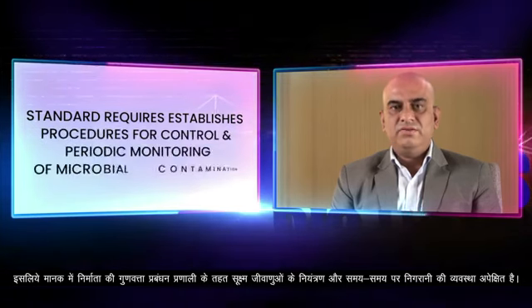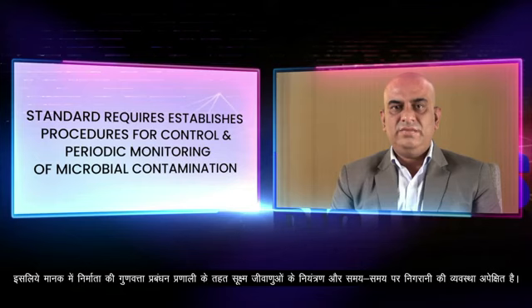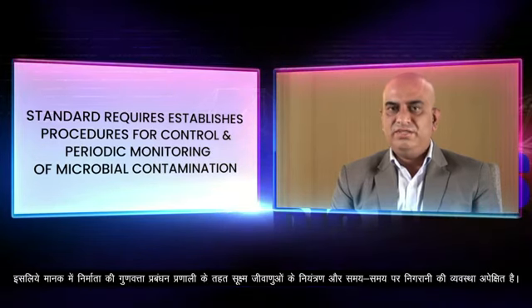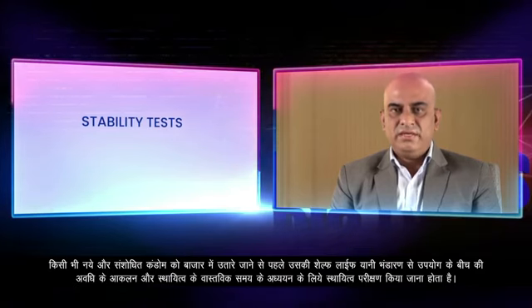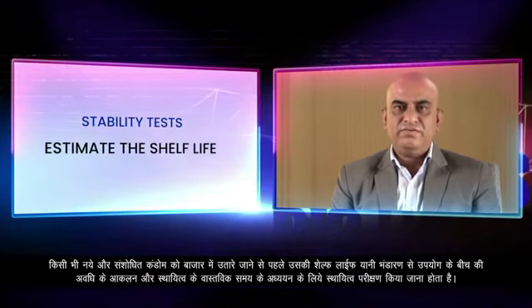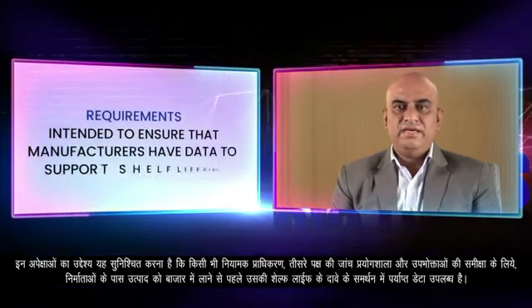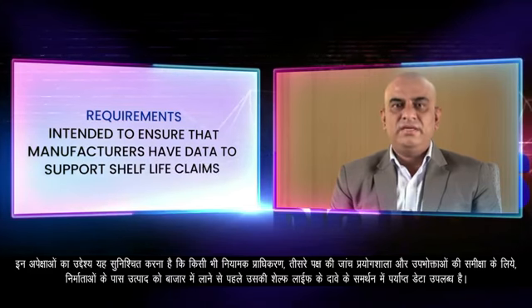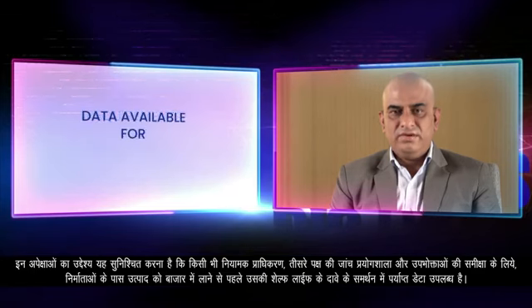Since some pathogenic organisms like Staphylococcus aureus, E. coli etc. can potentially be found on condoms and can cause urinary tract or other infections, this standard therefore requires establishing procedures for the control and periodic monitoring of microbial contamination as part of manufacturer's quality management system. The stability tests are to be conducted to estimate the shelf life of any new or modified condom before the product is placed on the market and to initiate real-time stability studies. These requirements are intended to ensure that manufacturers have adequate data to support shelf life claims before products are placed on the market, and these data are available for review by regulatory authorities, third-party test laboratories and users.